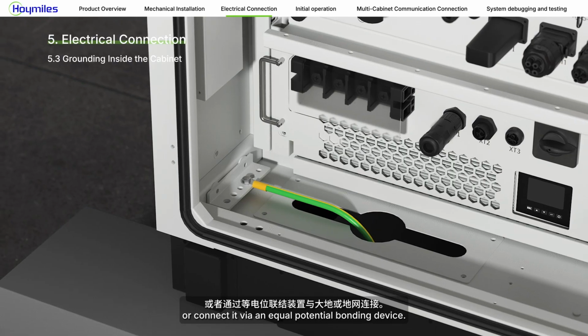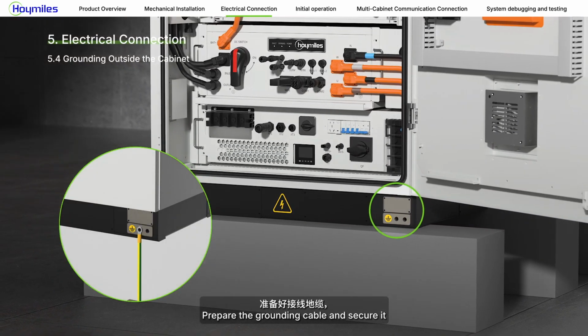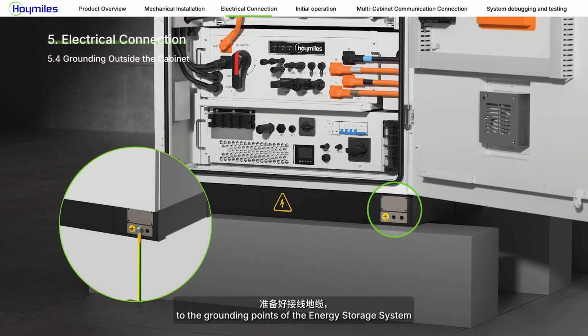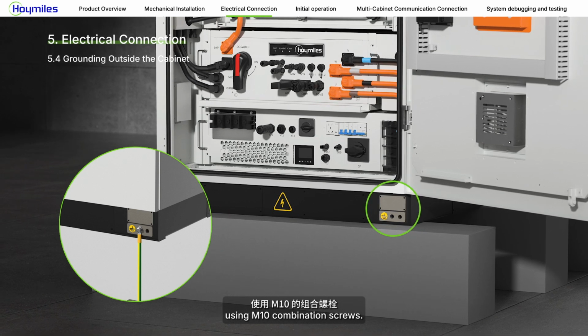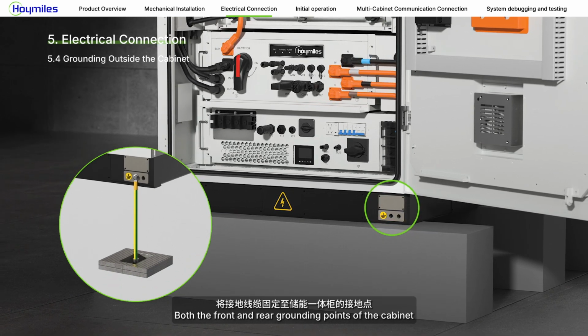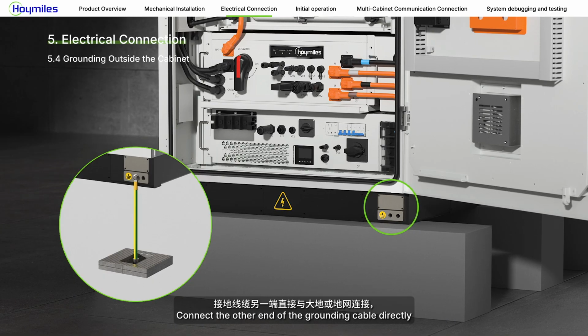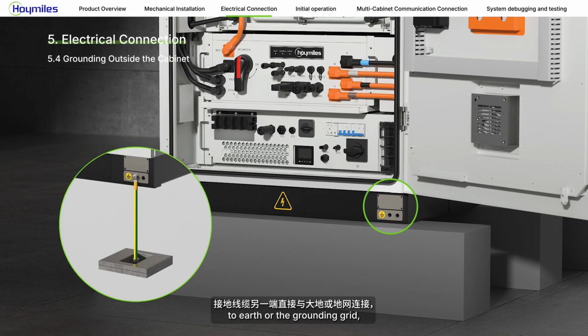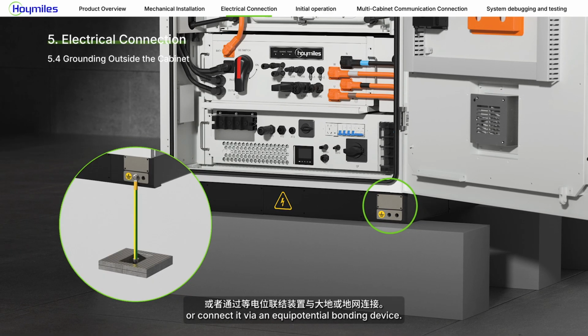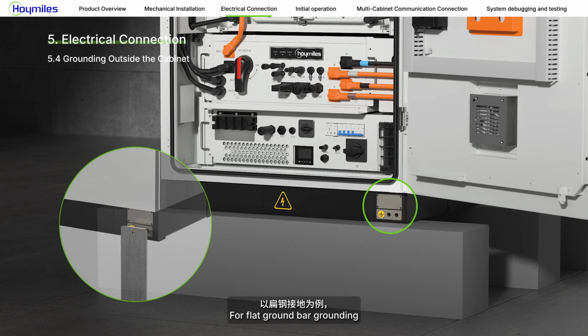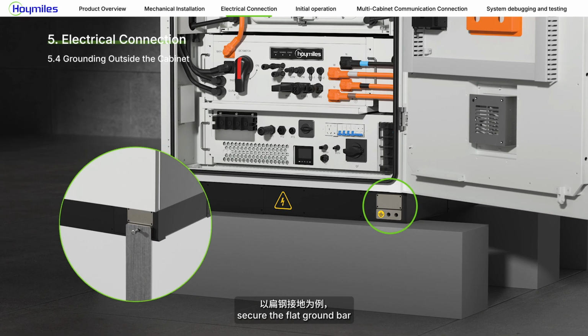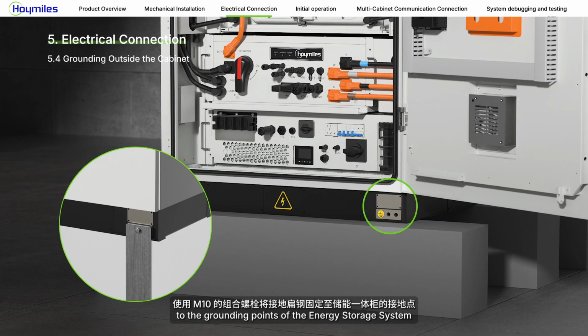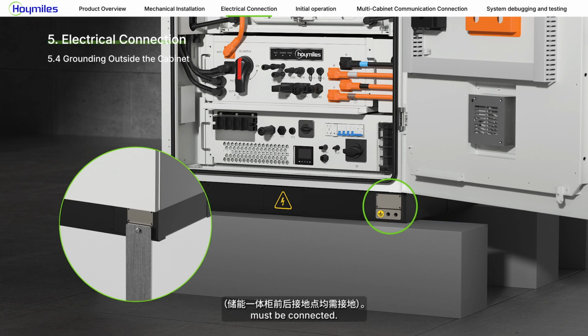equipotential bonding device. Prepare the grounding cable and secure it to the grounding points of the energy storage system using M10 combination screws. Both the front and rear grounding points of the cabinet must be connected. Connect the other end of the grounding cable directly to earth or the grounding grid, or connect it via an equipotential bonding device. For flat ground bar grounding, secure the flat ground bar to the grounding points of the energy storage system using M10 combination screws. Both the front and rear grounding points must be connected.